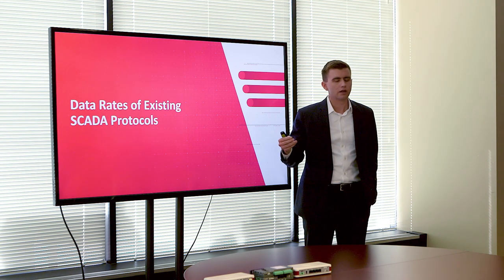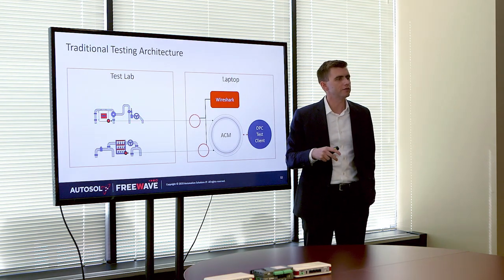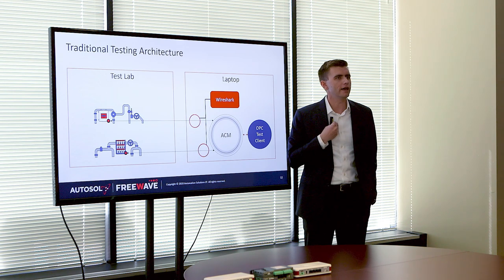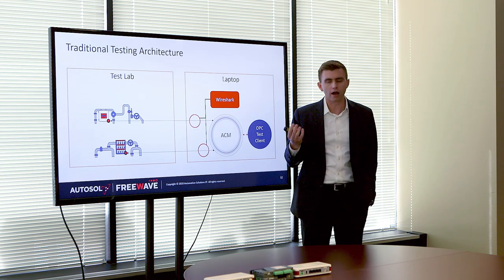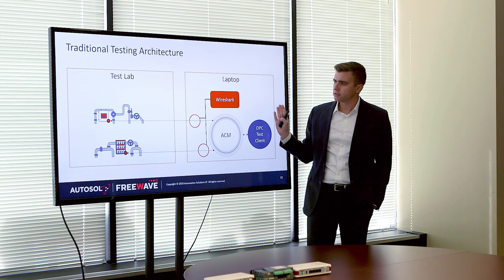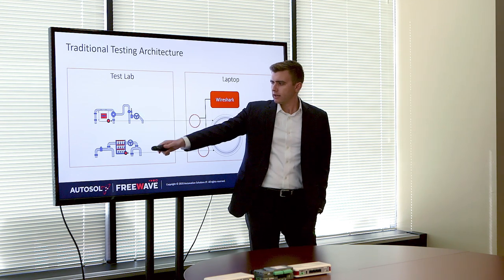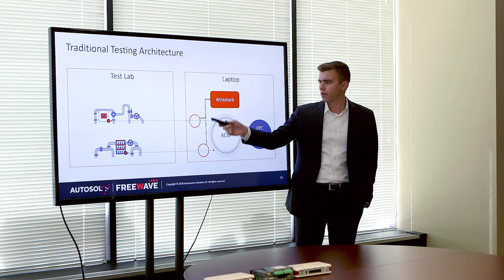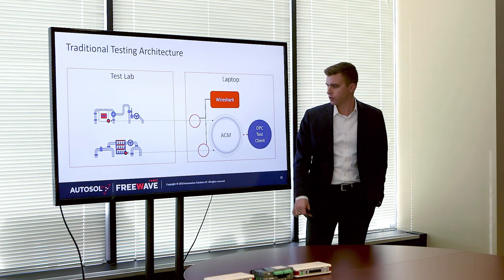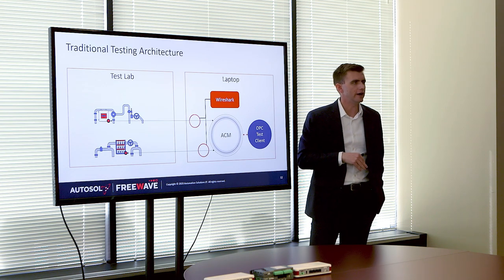I'm going to go through poll rates of existing protocols, focusing on Modbus and ROC. Here's the architecture we used to run this test in our lab: we have a Modbus device and a ROC device polling locally to our laptop, and we're observing bandwidth consumption via Wireshark. We're using ACM to poll and showing that data in OPC test client to verify that the values are correct.